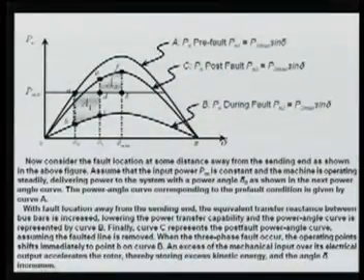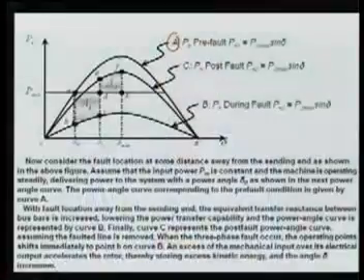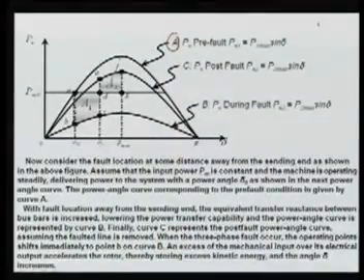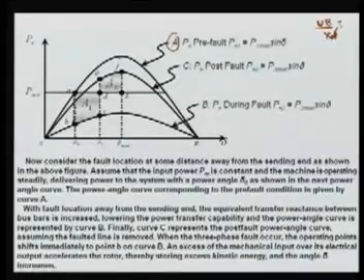So let your this curve A, outer curve from 0 to pi, and that is denoted by your A, and it is called the pre-fault curve. Means where all the impedances are intact, where X is your XD prime plus XT plus the parallel impedance of the 2 lines. Since impedance is less in that case, so what is happening? This curve will be higher. Why? Again you remember this is your VE upon XD prime, means X prime, simply sin delta. If this value is small, then PE will be larger magnitude. So it is outer where it is followed.